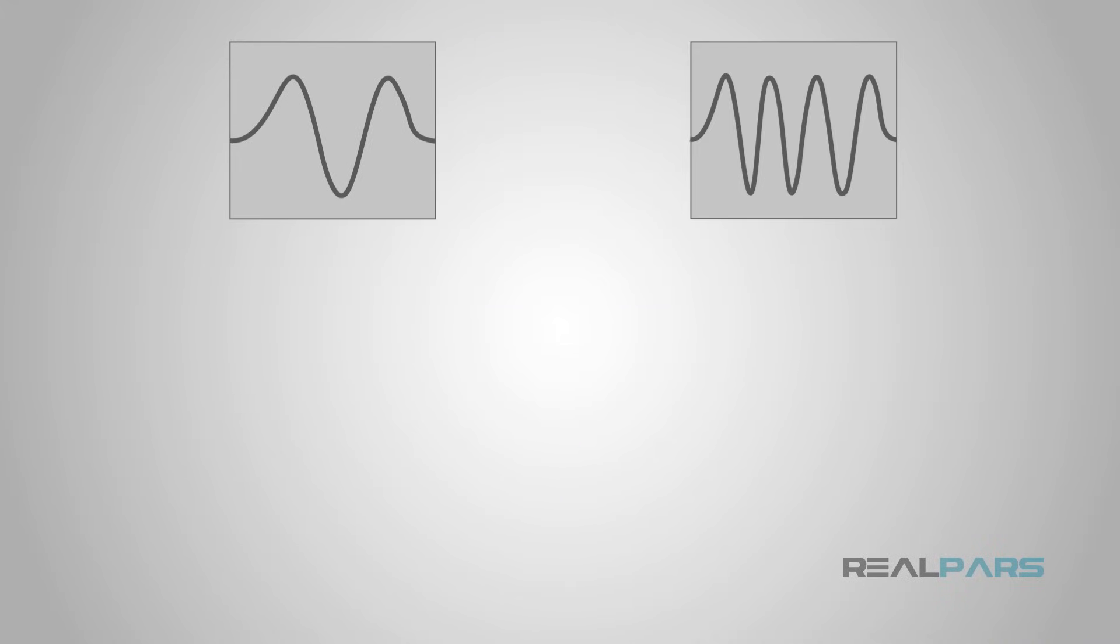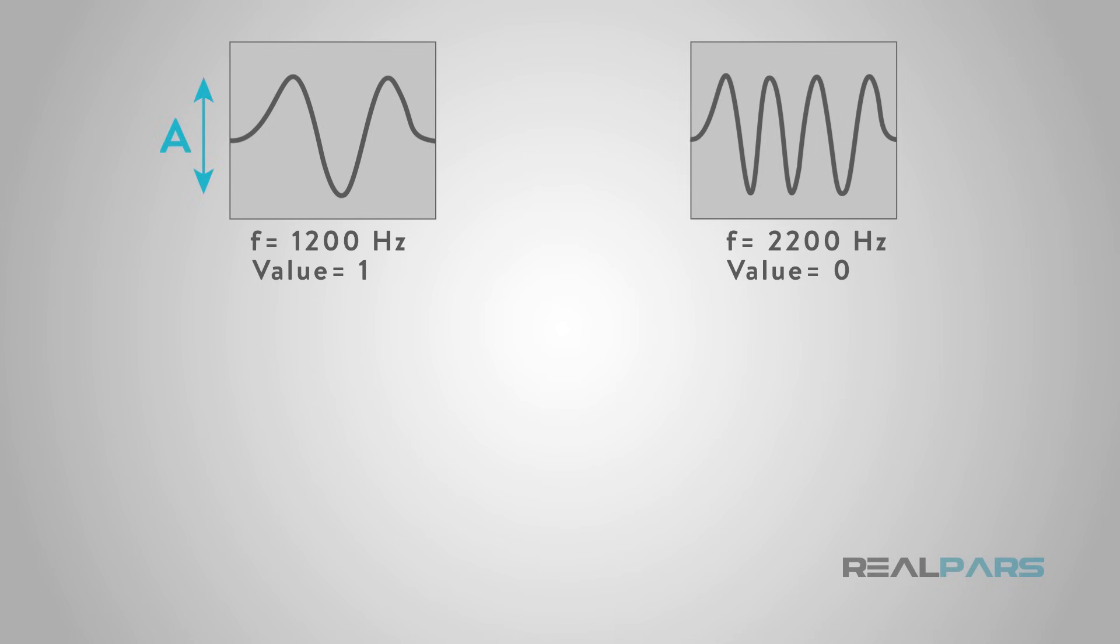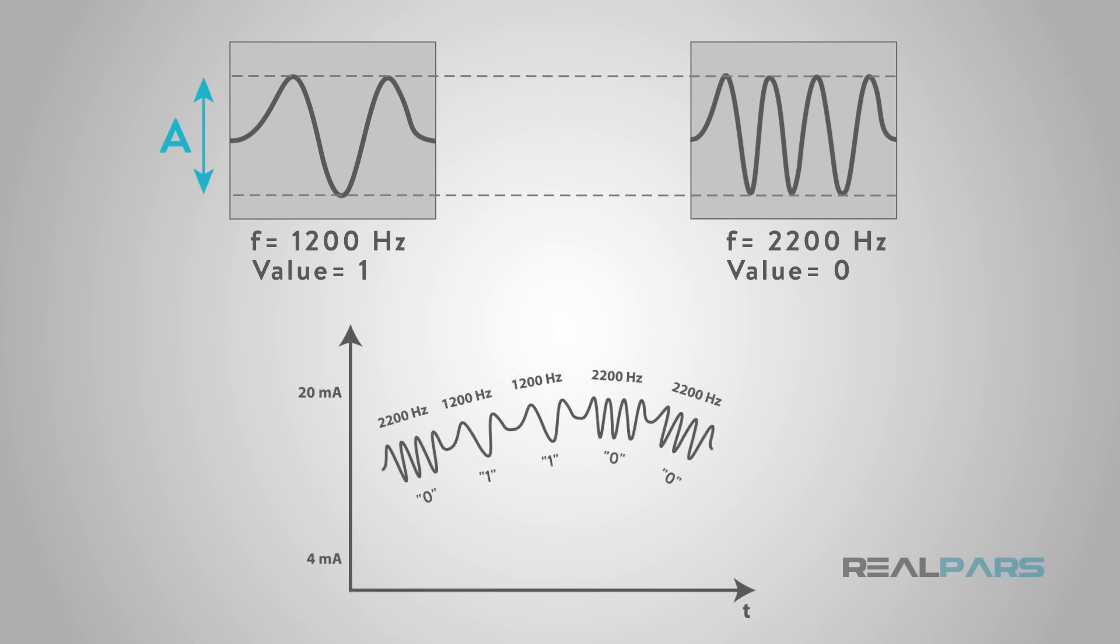The AC HART sine wave oscillates at either 1200 Hz for a 1 value or at 2200 Hz for a 0 value. The amplitude of the AC sine wave remains the same and for every oscillation, the amplitude of the first half of each sine wave above the DC current curve exactly equals the amplitude of the second half of each sine wave below the DC current.